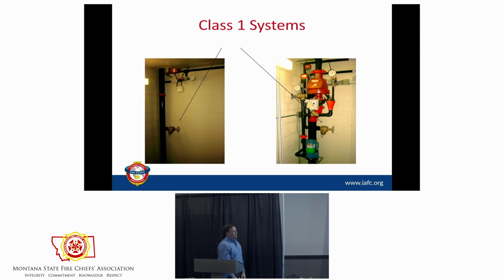So we have all sorts of different types of standpipe systems that our crews need to be able to work with. When you see ones like those, who's it intended to work for? Us. Right. Now, not all codes require adequate pressure for you to operate. So if it's not considered a high-rise, standard pressure applies, and they can do what's called a manual wet pipe standpipe. What does manual mean? You provide the pressure. Okay? So if it's manual wet, I might have 60 or 70 pounds. It's enough to get started, but are you really going to be pleased with your nozzle? Probably not. When you get into high-rise situations, then you will have pressure-reducing valves. You'll have all the difference.